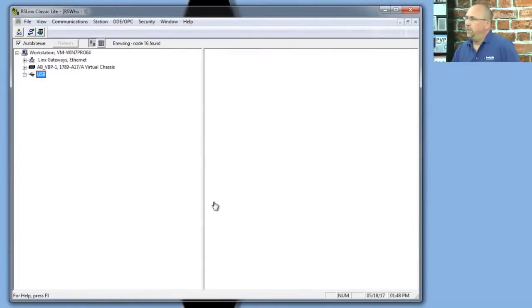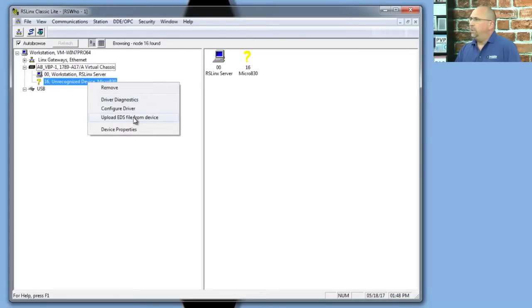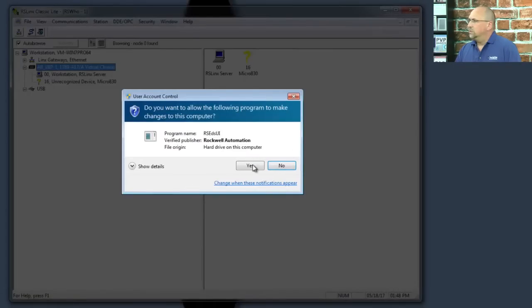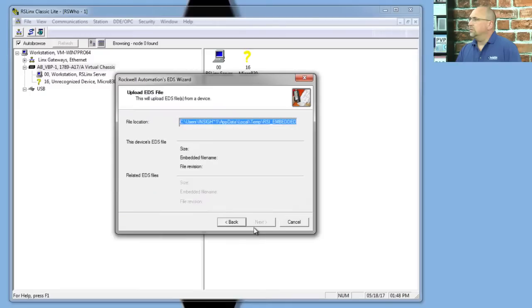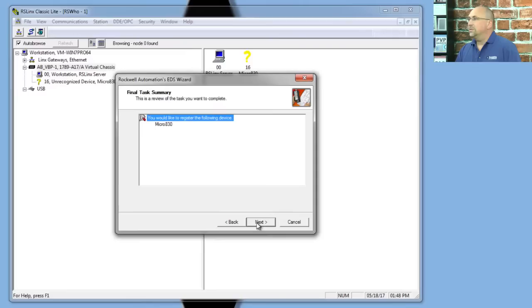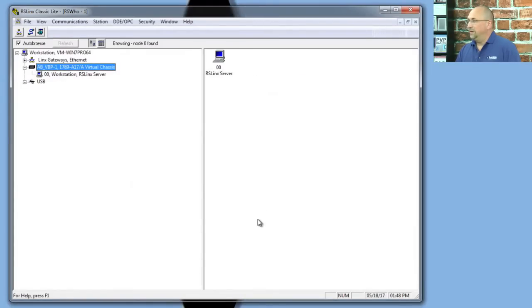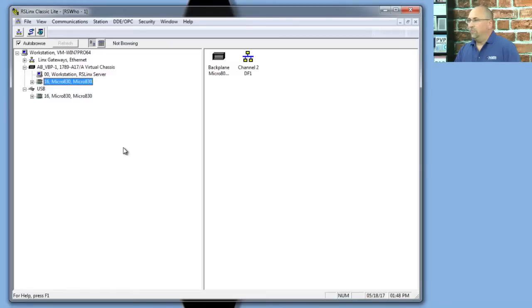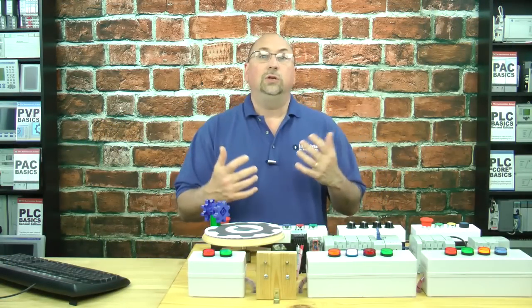In that case, you'll want to expand the virtual backplane, then right-click on the Micro and select Upload EDS File. Select Yes, then Next through the wizard steps, and Finish. In a few moments you should see your Micro 800 show up in RSLinx Classic's RS Who. And that's how easy it is to communicate between your Micro 800 and your PC using USB.